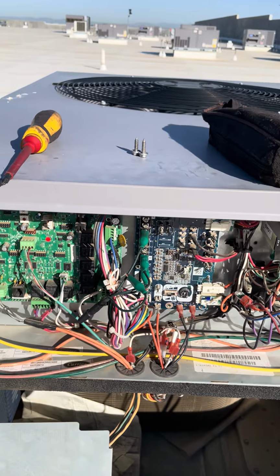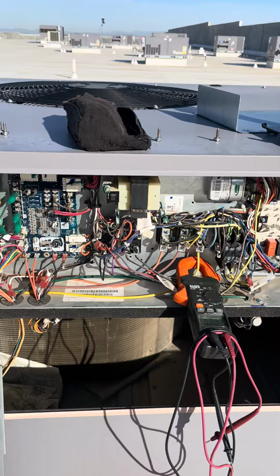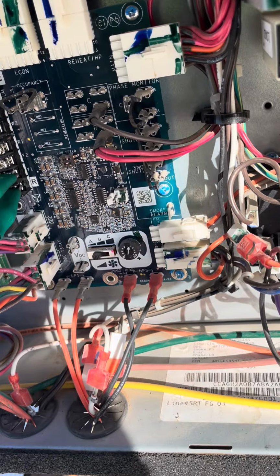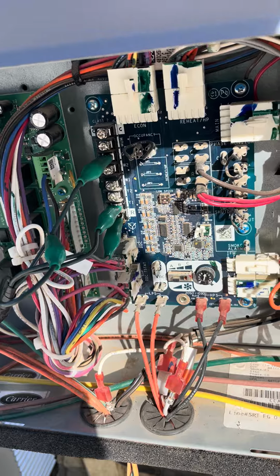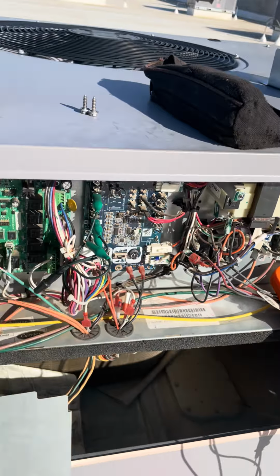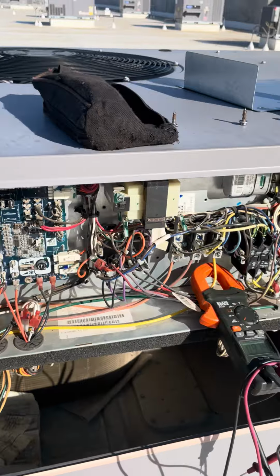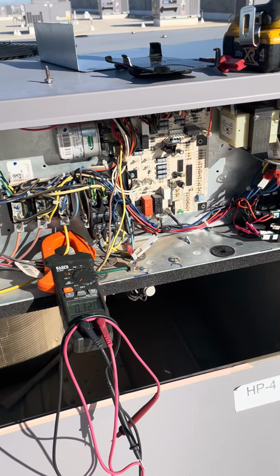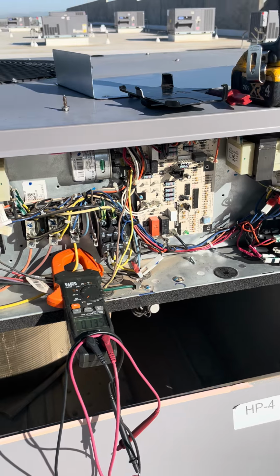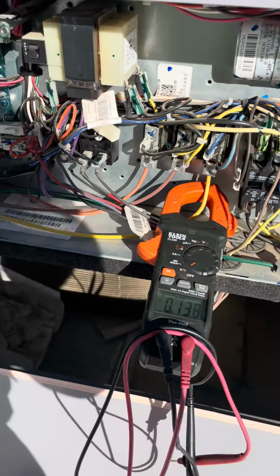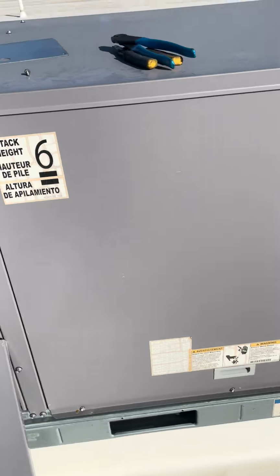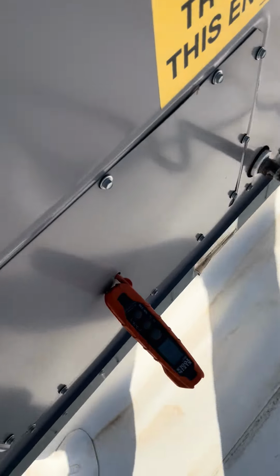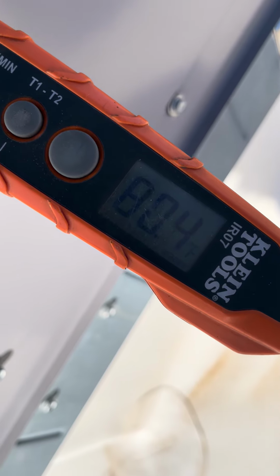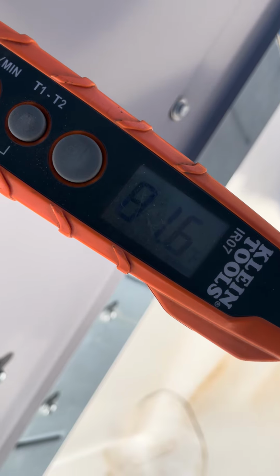So I'm going to turn it on and show you, because right now the unit is jumped out for the cooling mode. So we're going to turn it on. Sequence of operation: compressor, then we turn on the condenser fan and then the blower on the inside. So we're going to see the temperature. Temperature rising, and we're in cooling mode. So it's a heat pump, and the reversing valve is not being energized right now.